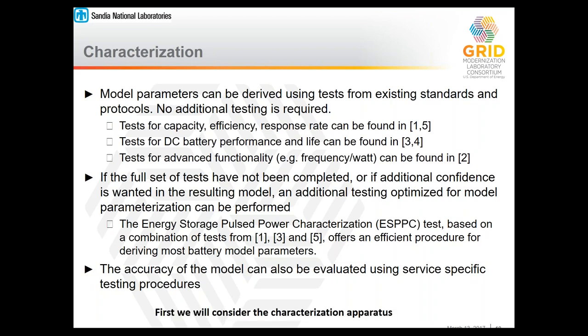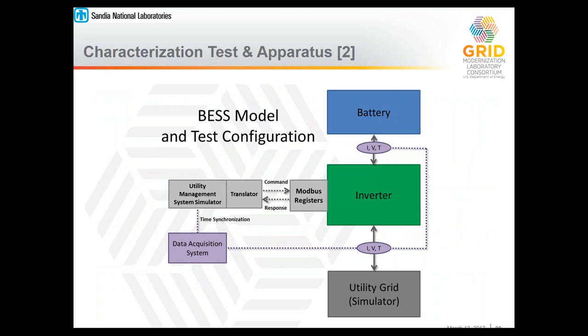So first we will cover the characterization apparatus, how we actually set the devices up to run these tests. Essentially, in the laboratory, we set up the utility simulator and the battery and inverter system, and then we place measurement both between the battery and inverter and between the inverter and the grid. We time synchronize that data acquisition system with a utility management simulator that translates and sends commands to the inverter for the charge and discharge, for the power command with battery limits manual control mode. This is how we set it up in the lab, and it's important to get temperature, voltage, and current measurements from both the battery and the inverter because that's really important for understanding the physics of what's actually going on.